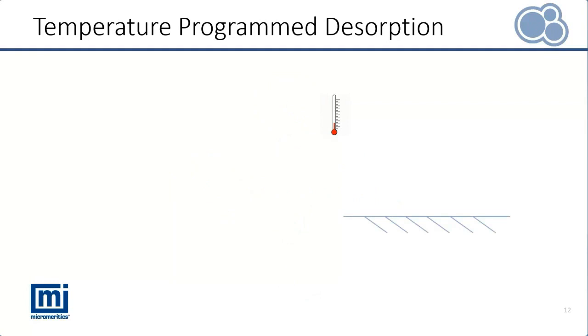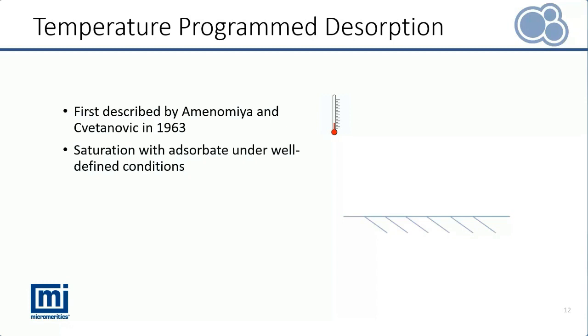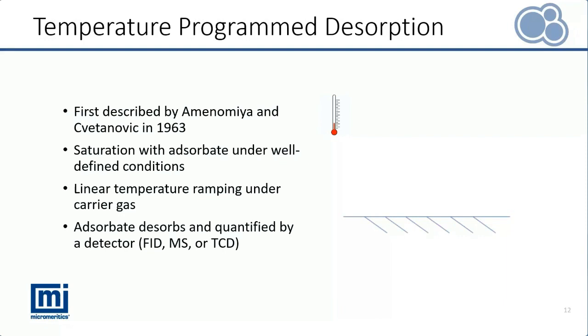The temperature program desorption was first described by Amenomiya and Cvetanovic in 1963. As for the experimental procedure: first, saturation of the surface of a sample with an adsorbate under well-defined conditions is required, followed by linear temperature ramping under a carrier gas. The adsorbate desorbing as the temperature increases is quantified by a detector such as FID, mass spec, or thermal conductivity detector. All the TPD data shown in this webinar were analyzed on the Micromeritics AutoChem 3, which is equipped with a TCD detector.